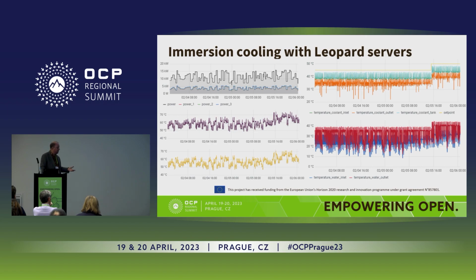And all of our test rigs, this is only one of the test rigs that we've been running with, are all connected to the same data collection system. And if we can measure it, if we've got a sensor, we put a sensor in. If we've got the sensor data, we go for it. So IPMI data, Redfish data, we get access to all the server data. And this doesn't really show much, but it shows a workload on the data center there, because these 54 servers at a maximum peak of 400 watts, you're around about 22 kilowatts in the tank, but we're running with about a 50% workload there, but it's fluctuating.